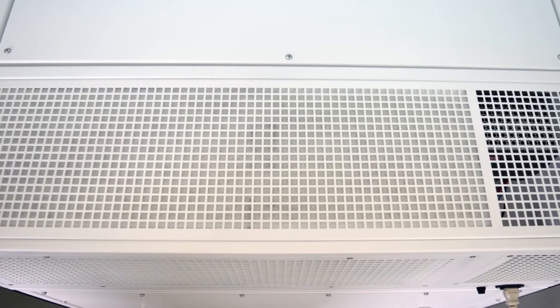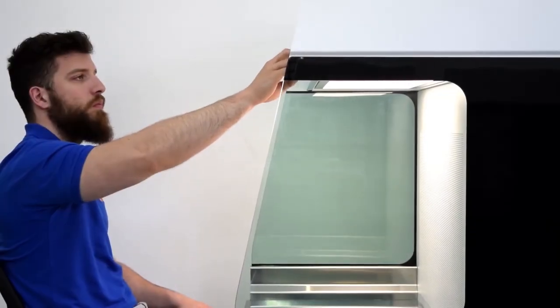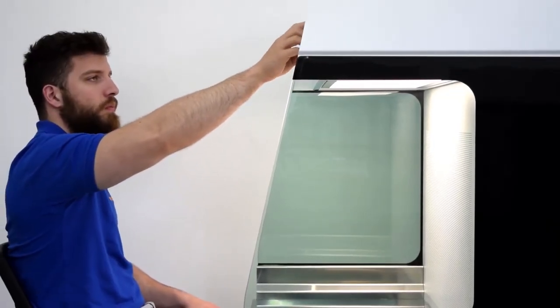The cabinet has one motor on the back side which draws the outer air in through the pre-filter. The main HEPA filter is filtering 99.95% of the particles bigger than 0.3 microns in diameter. This safety level ensures clean, dust-free conditions in the working area.